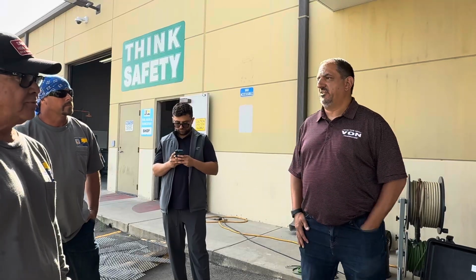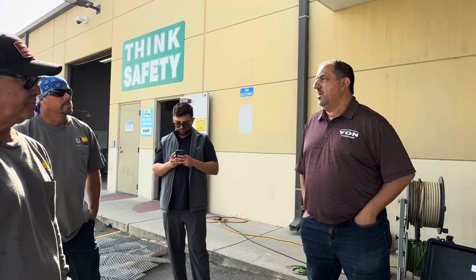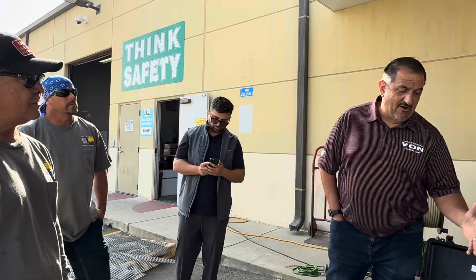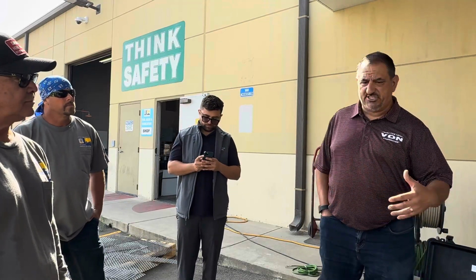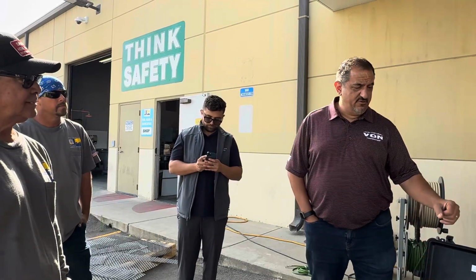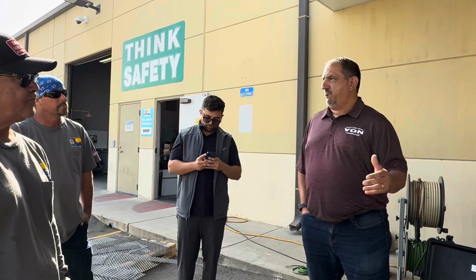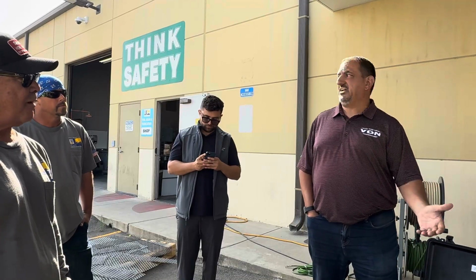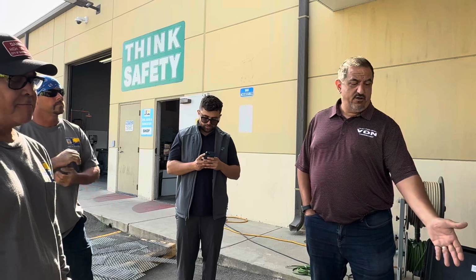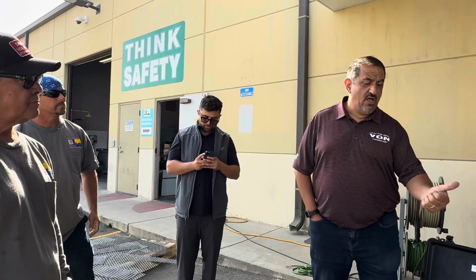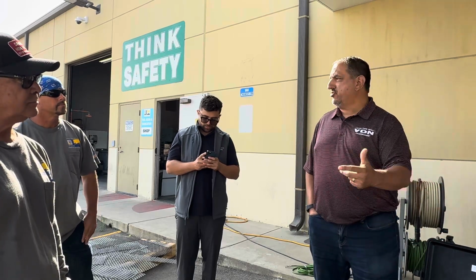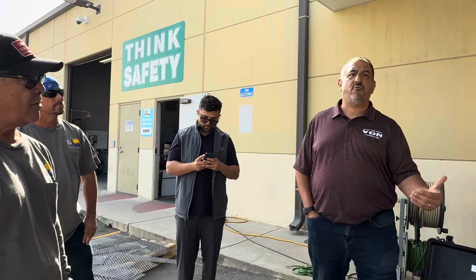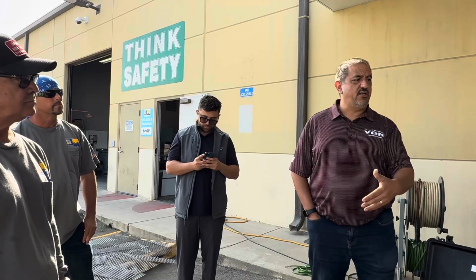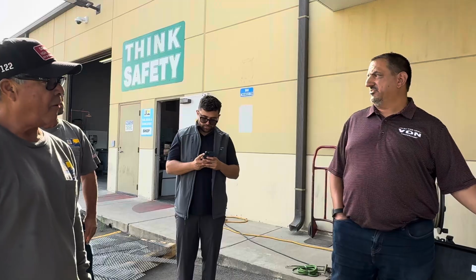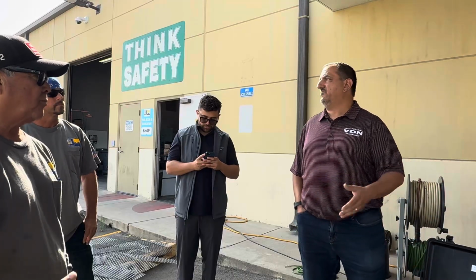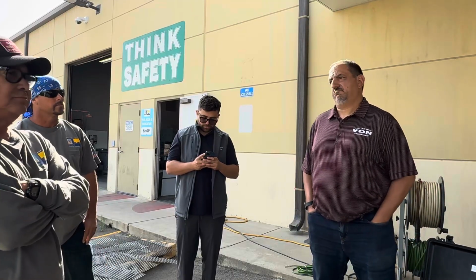So you just need to be aware, only one at a time. Because what you should do—I don't know what your processes are here, but let's say you find the fault and fix it—before you leave, you should test it again. You can test it with your hipot test, go to radar, go to thump, but you should take it to whatever voltage you want to verify there's no other fault, because you have no way of knowing if there's an additional fault.